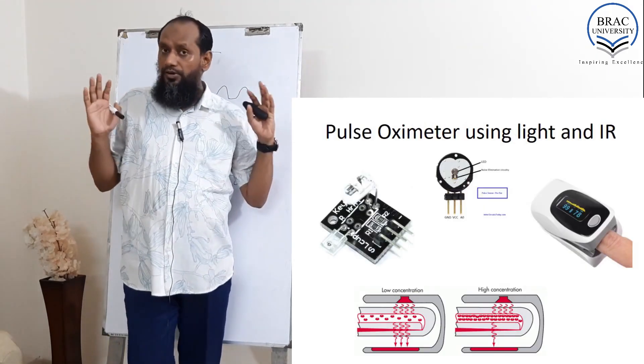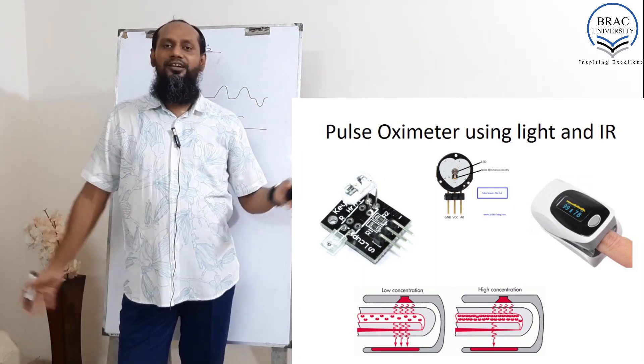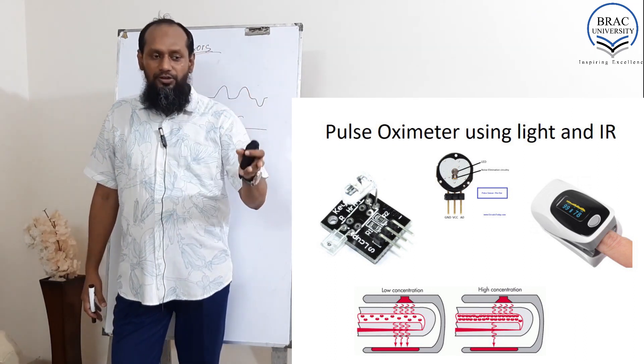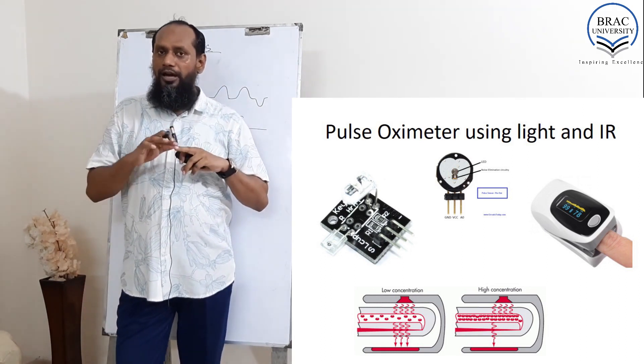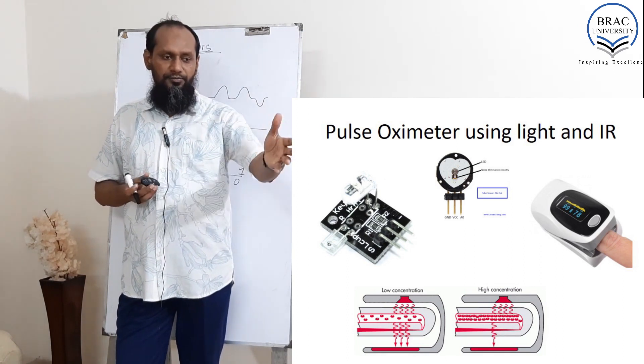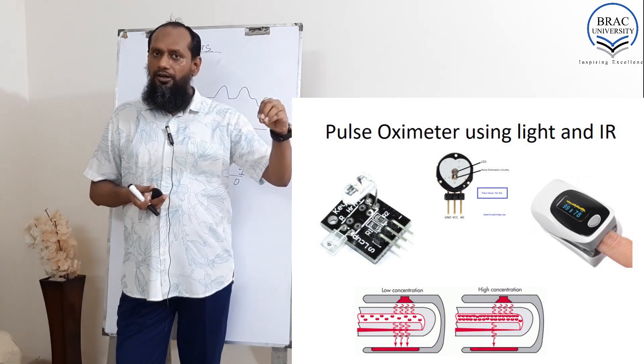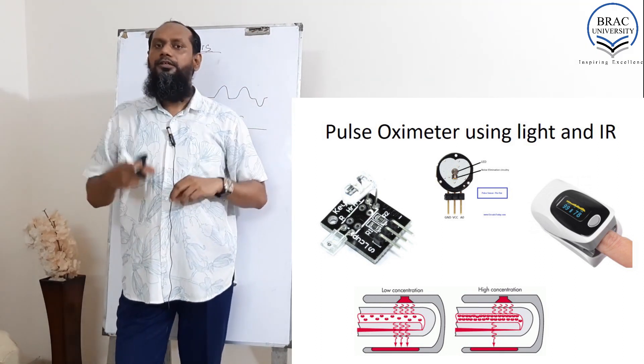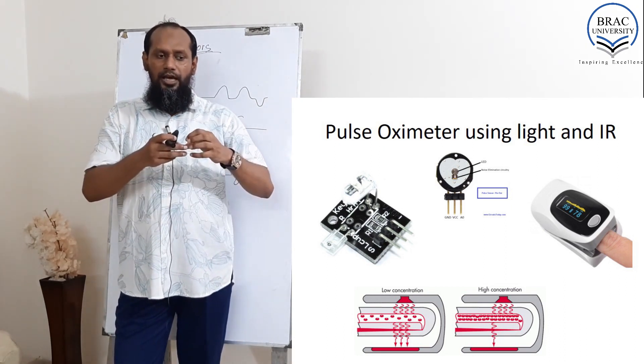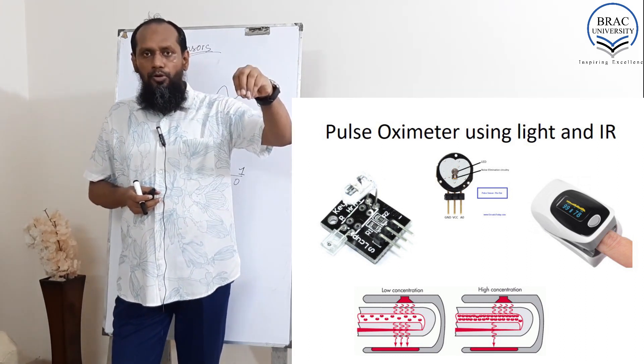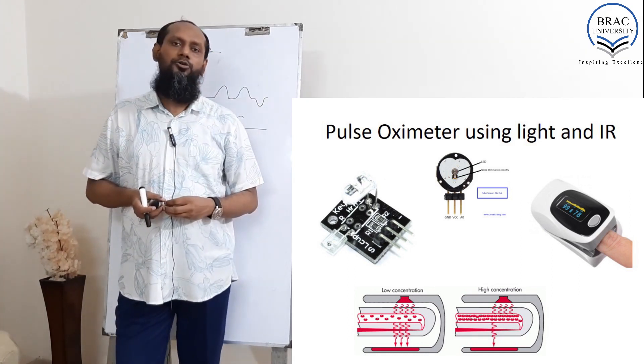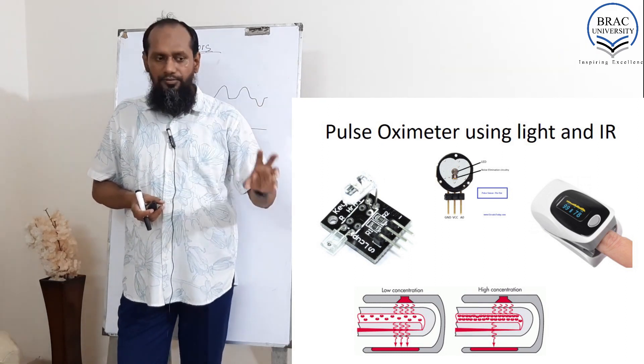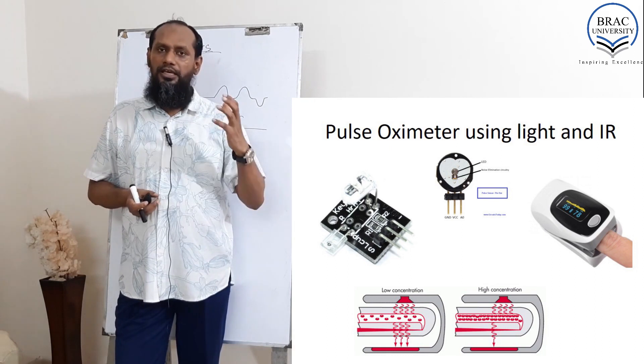The pulse oximeter is a very commonly used sensor. You can observe the blood flow or the red blood cell flow. In the first figure, the amount of red blood cells or oxygen was low, so most of the light could pass through the vessels. In the second figure, since the amount of red blood cells increased, almost no light could pass through.